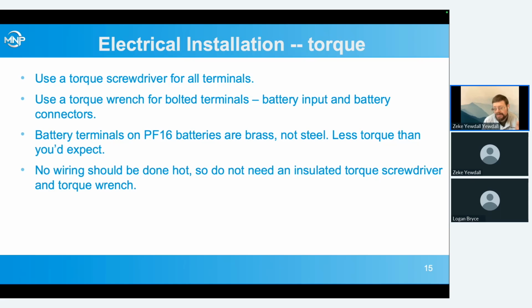They don't have to be these special electrical rated ones, because none of this wiring should be done hot. If you're doing hot wiring on the system, something went wrong in your order of assembling it. You should never be doing that. When you're doing troubleshooting and taking apart old systems and things involving lead acid batteries that you can't just turn off to do the wiring, then you do end up doing hot wiring, and you'll want insulated equipment. But none of the wiring on this inverter should have to be done hot, so you should be able to use a regular torque screwdriver and a regular torque wrench, somewhere $100 or less for each of them, and it's just something to have in your toolkit.